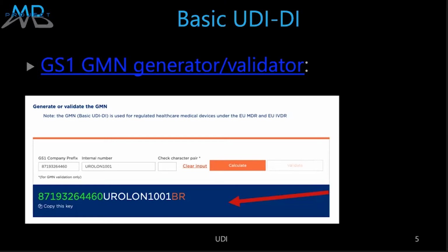In general, you could say that if you have one technical file or technical dossier, that will have one basic UDI. Yeah, that's what I was trying to tell them. Like examples I gave, suppose some ortho implant of one type, then it's fine. And then you have it in 1 mm, 2 mm, 3 mm, 4 mm diameters.